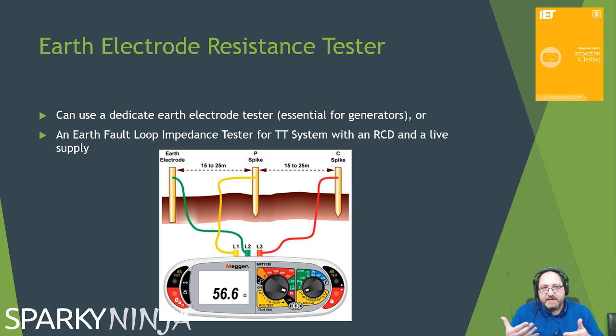Okay, but again, it's just another method of using a high reading ohmmeter, like an insulation tester. Some people might call it an earth megger. It's like a DC generator applying a voltage into the ground. The difference with the electrode resistance tester is you need more ports for more probes to get the reading through the soil. So it's a slight adjustment to the normal insulation resistance test.